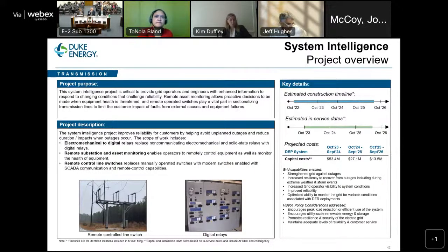The historical means of finding a fault on a transmission line: think of a long line, maybe 30 miles or more. When we have a fault and no intelligent devices telling us where it occurs, our energy control center only knows that the breakers on each end of the line opened. Somewhere in the middle of these 30 miles we have a problem, and we have to dispatch linemen to start driving down right-of-ways, which in some cases are very difficult to access since they're not generally along roadways. With intelligent devices, we have a better idea, in some cases a very specific location down to the structure number where the fault occurred.